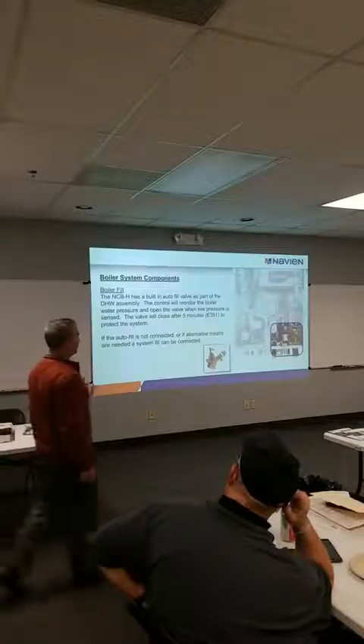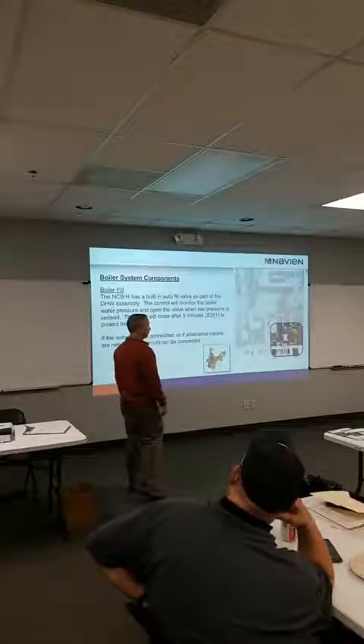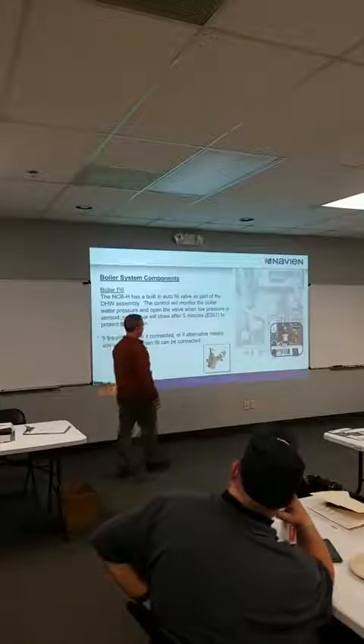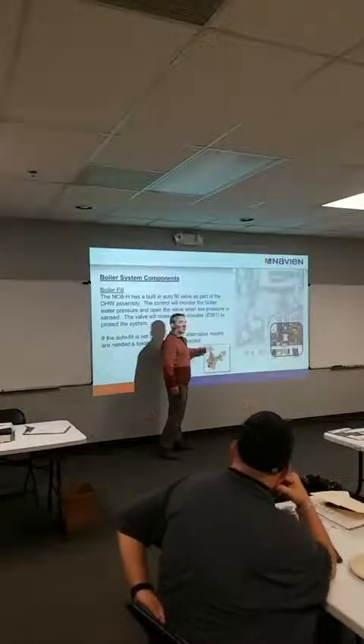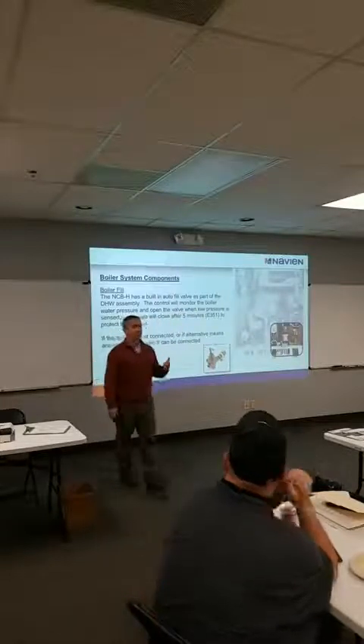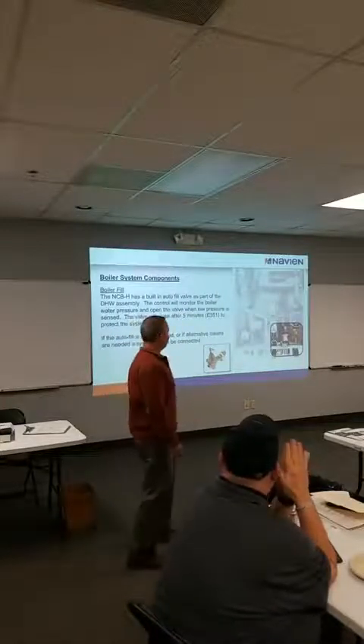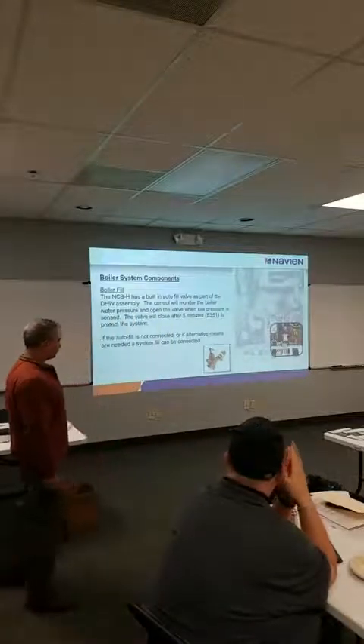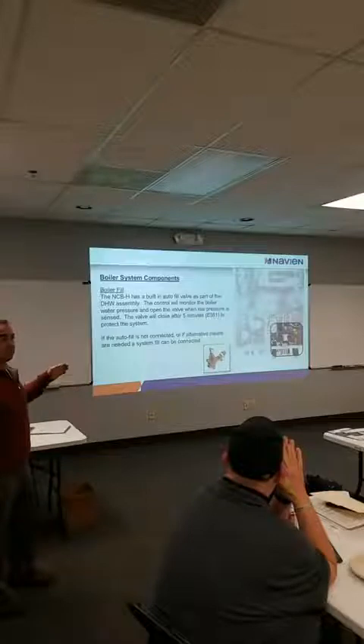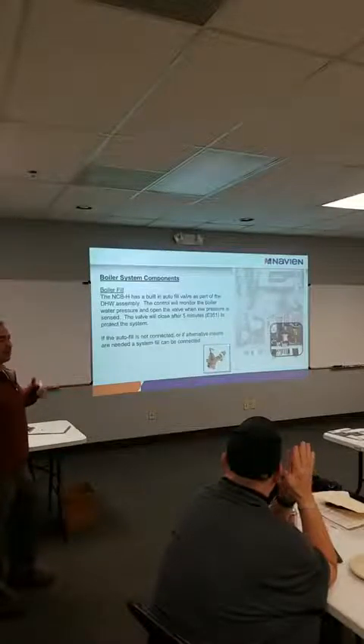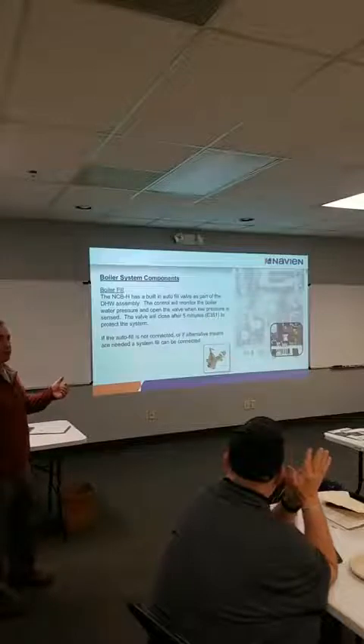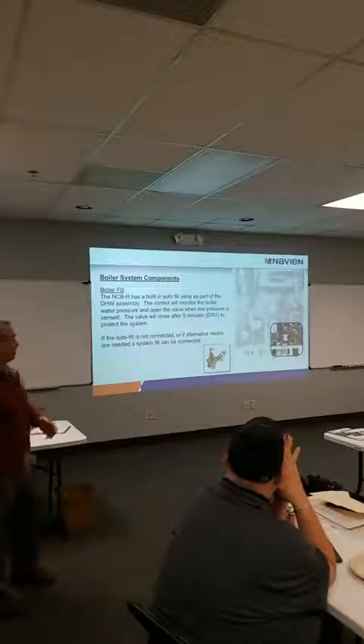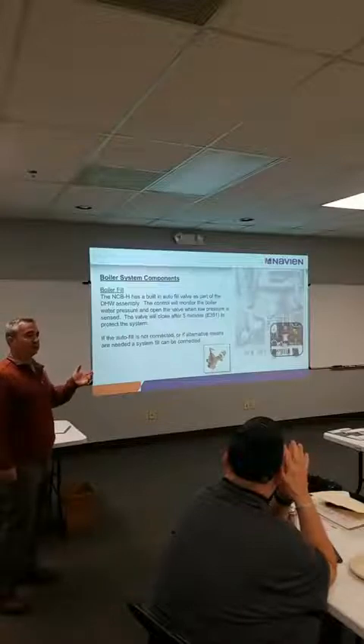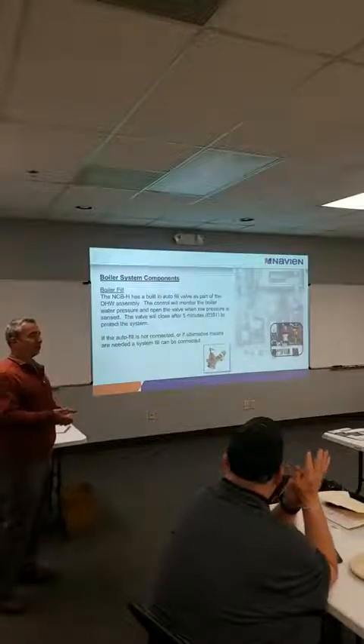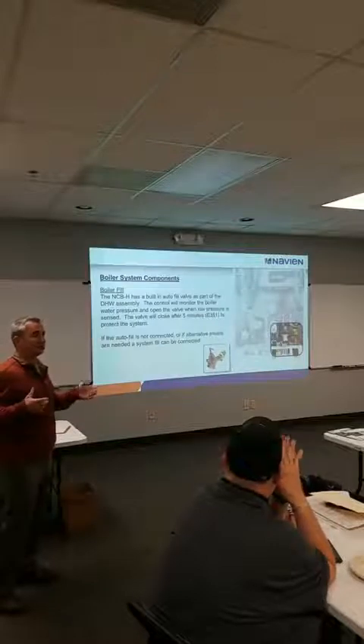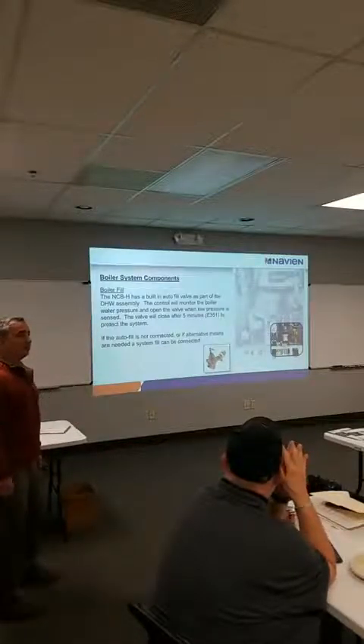Our unit has a built-in autofill valve, all the combis do. So if you're on a job and there's an autofill valve, you just open this all the way up so we see street pressure, and then you can set pressure internally to the system wherever you want. Default's 12 pounds. It is not mandatory that you pipe into our boiler inlet, but I think it's added protection to the system so we can see, number one, what our inlet pressure is. If we have a leak in the system, it'll autofill that system. But if you do have a leak and it autofills more than 5 times, it shuts the system down to protect it and throws an error code. So you go find your leak instead of just continually autofilling.